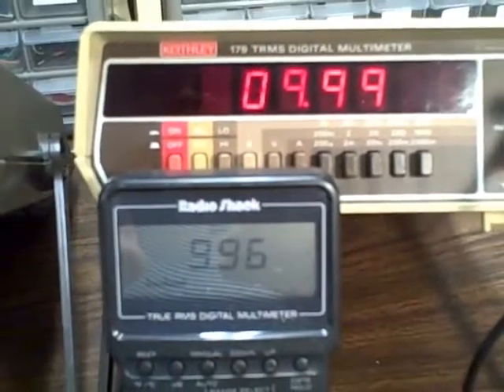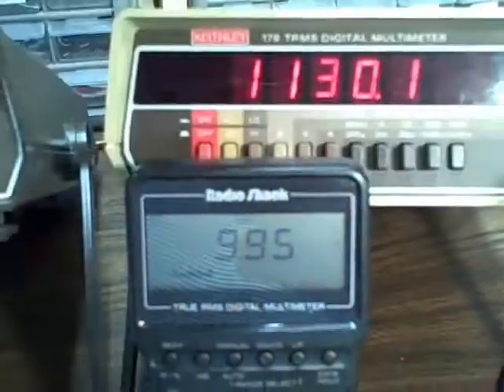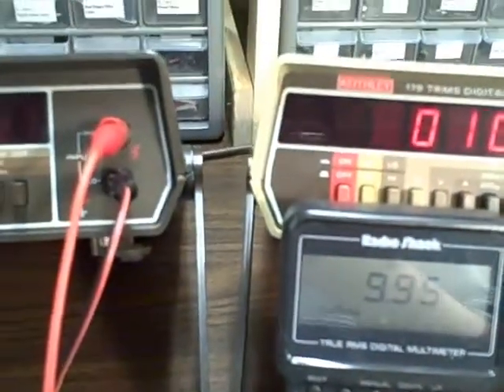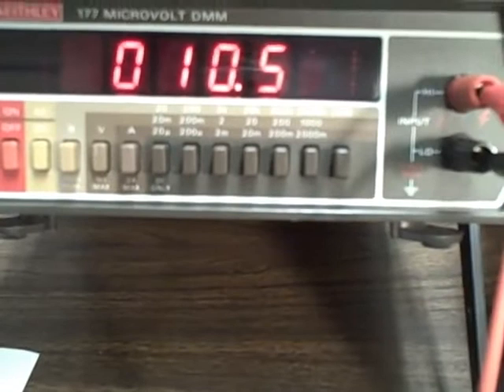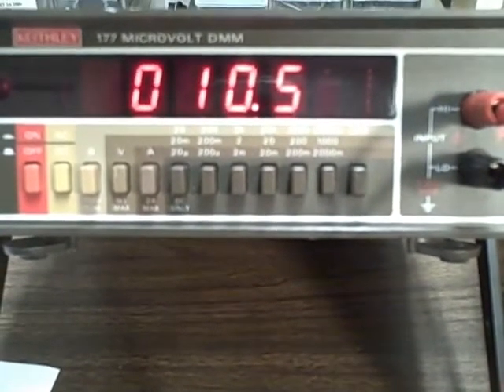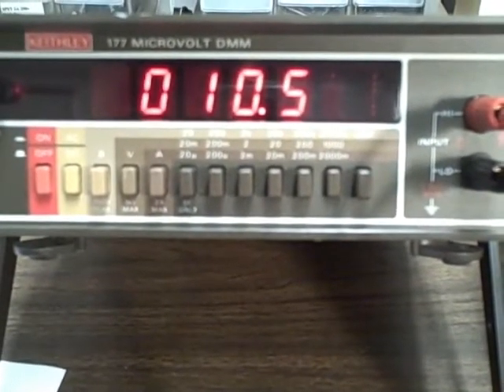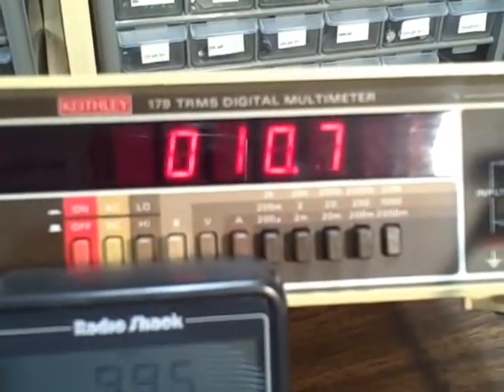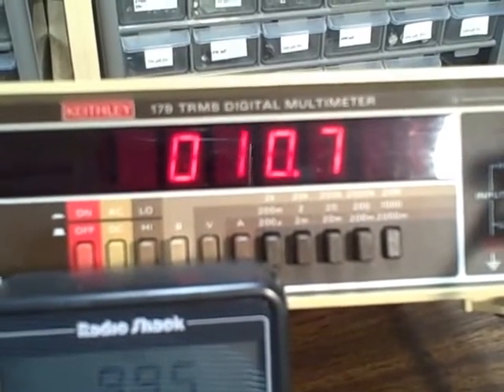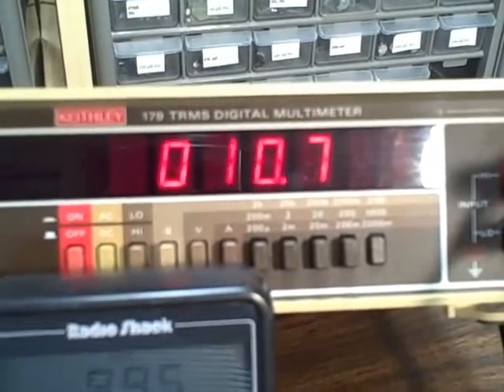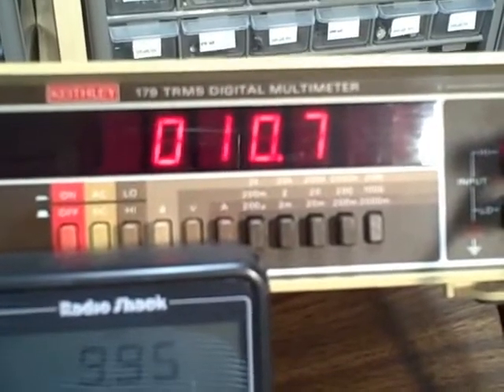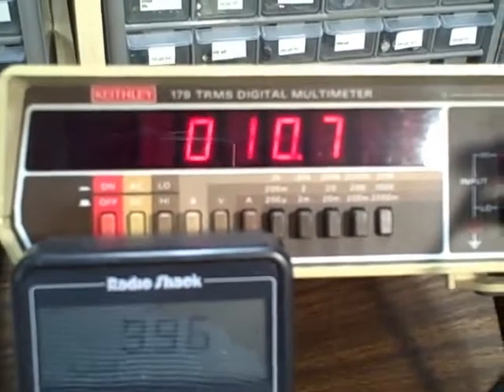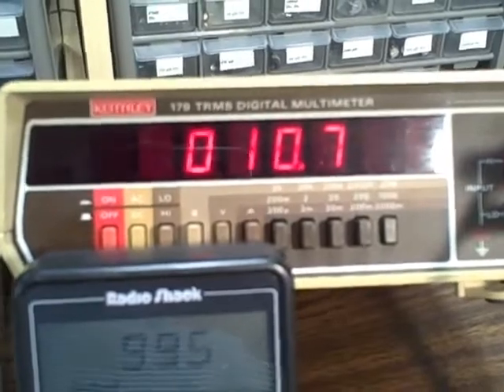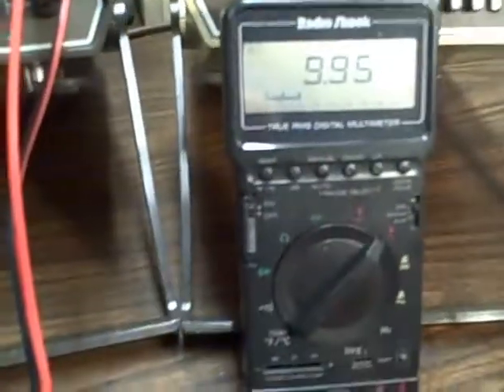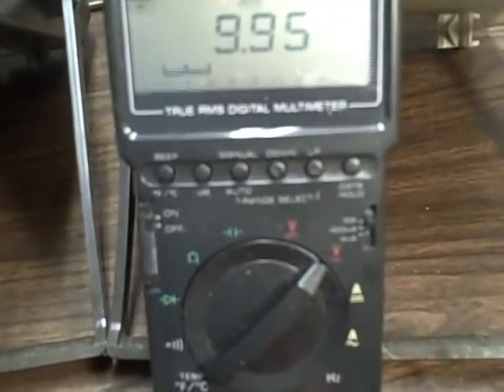And then at the 1000 volt range, I got 10.5 or 6. Let's say 5. And I've got 10.7 on the 179, maybe 0.6. So it's within 1 or 2 tenths of a volt at this range. Let's see, 2. And the Radio Shack is now reading 995.